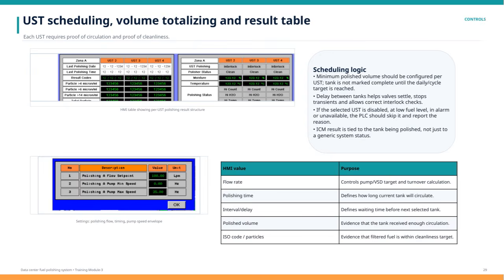When it comes to scheduling logic, there are a few important rules. First, a minimum polished volume must be set for each UST, and the tank won't be marked complete until this daily or cycle target is achieved. Second, a delay between tanks is necessary. This helps valves settle, prevents transient issues, and ensures the interlocks function correctly. Third, if a tank is disabled, has low fuel levels, triggers an alarm, or becomes unavailable, the PLC will skip that tank and log the reason. Lastly, it's important that the integrated control module's results are attributed to the specific tank being polished, rather than a general system status, so accountability and accuracy are maintained. In summary, this system ensures that each UST undergoes thorough polishing with clear verification of fuel circulation and cleanliness, supported by precise scheduling and control logic for optimal performance.